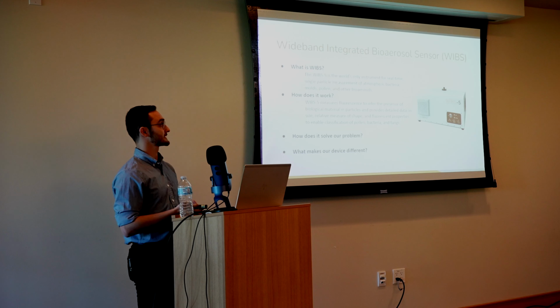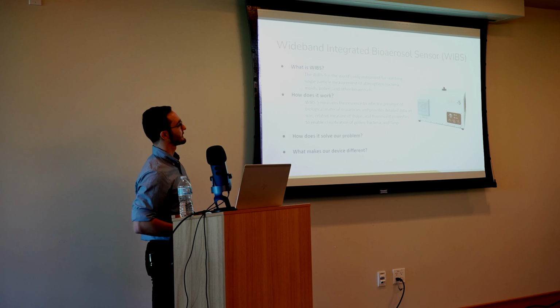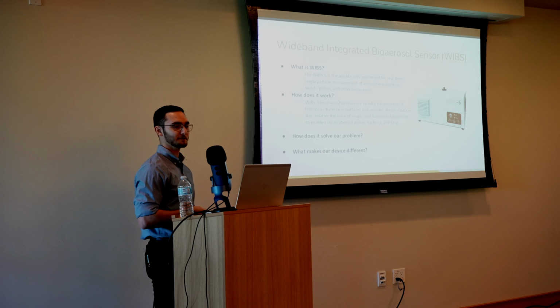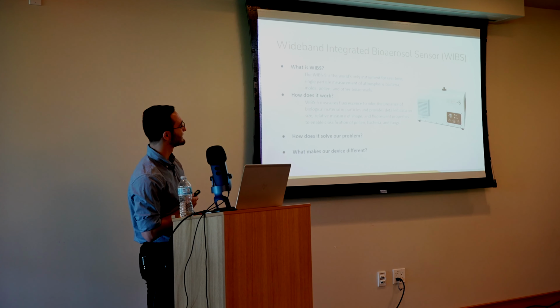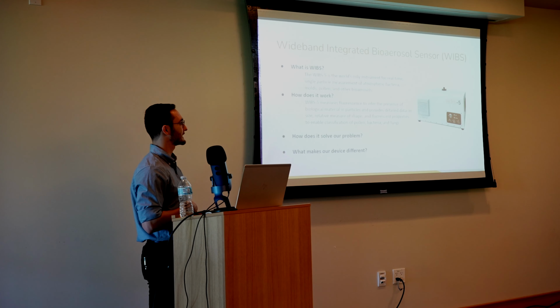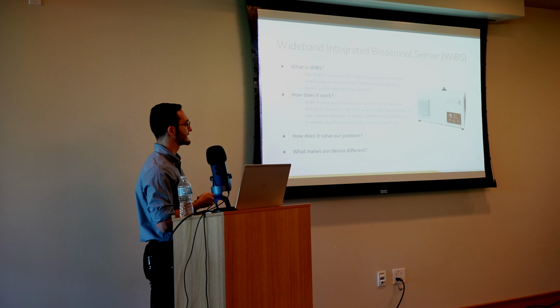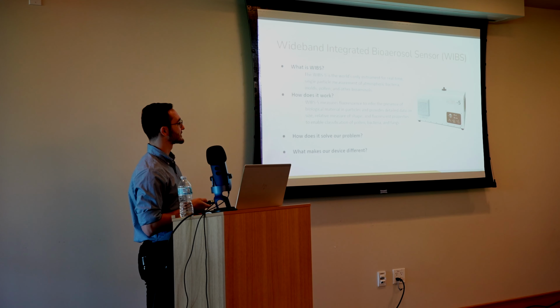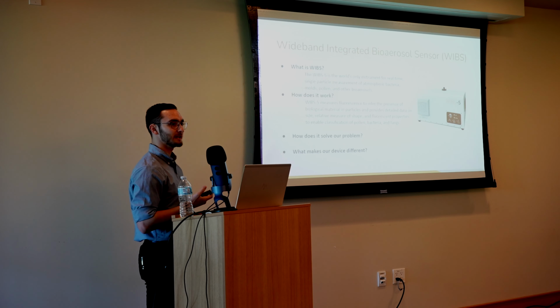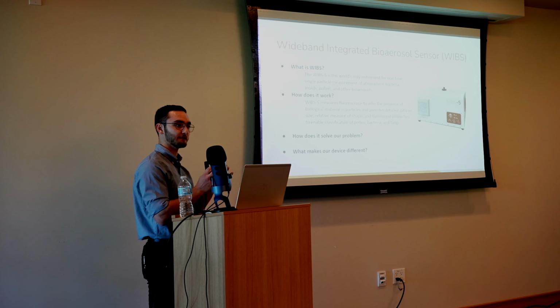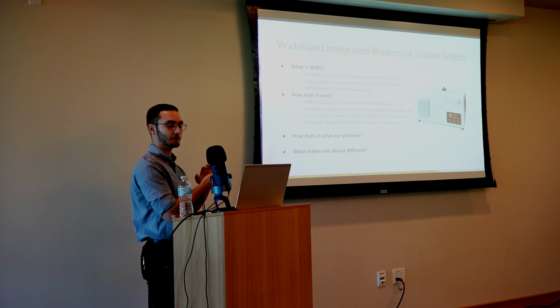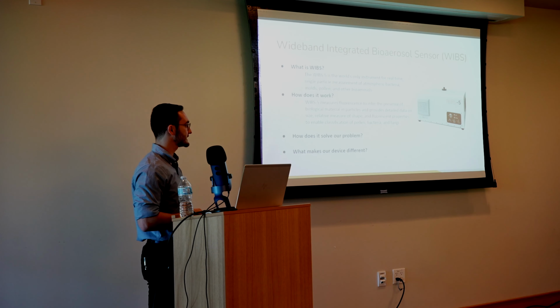So what is WIBs? WIBs is the wideband integrated bioaerosol sensor. Quite a mouthful, so I'll call it WIBs. This is the instrument that's going to be doing real-time measurements for these biofluorescent properties and a couple of other factors that we'll talk about for how it identifies these particles. It's going to be measuring a relative measure of shape, so we'll talk about the asphericity factor, how fibrous the particle is versus spherical. We'll talk about the bioluminescence properties, let me rephrase that, the fluorescent properties, and the particle size itself.